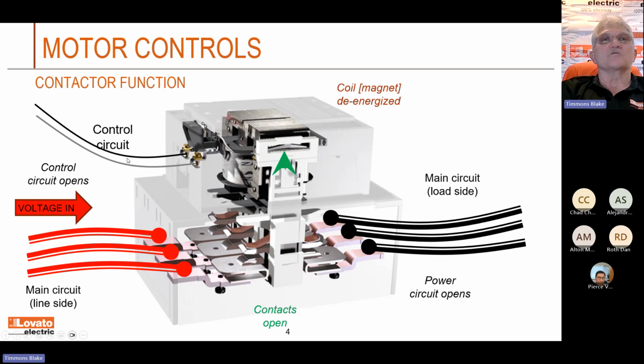You turn this control circuit off and on. And a lot of times, or almost every time, you'll run it through a set of overloads. So when that overload sees too much current, you'll turn the motor off right here at the coil.